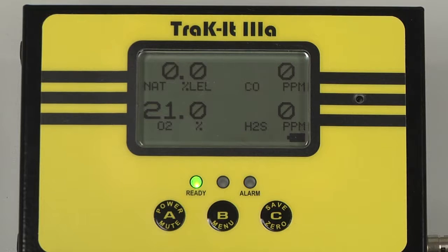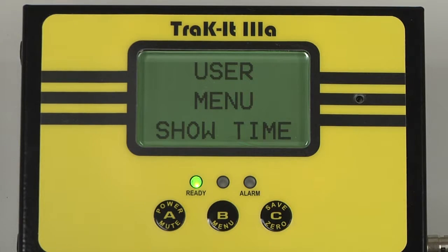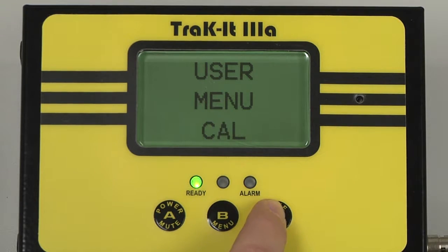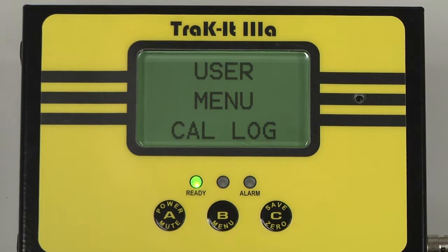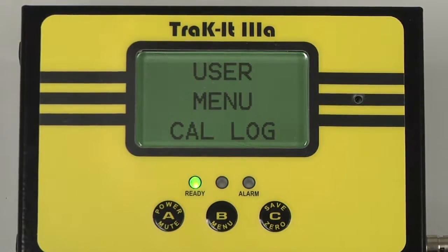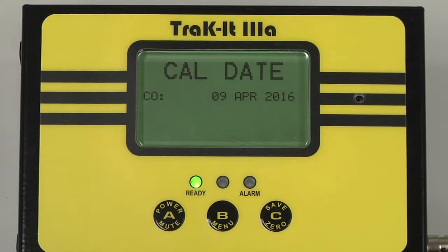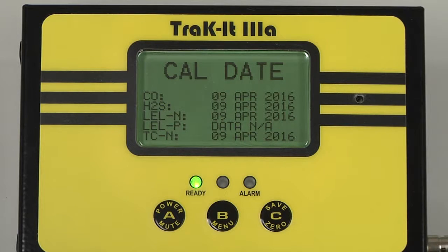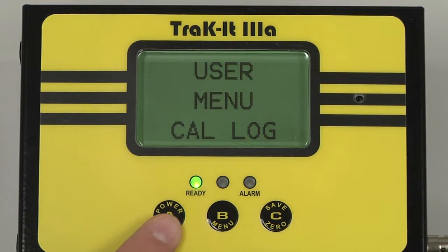To verify the calibration date, enter into the user menu by pressing and holding the B button until user menu is displayed, and scroll by pressing and releasing the C button until cal log appears. Select by pressing and releasing the B button, and the most recent calibration date for each sensor or gas type will be displayed. To exit, press and release the A button, and again to return to the working display.